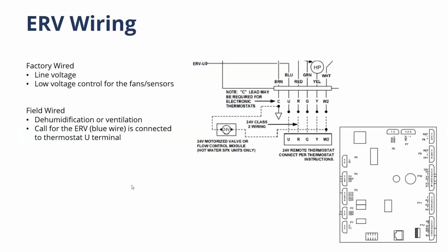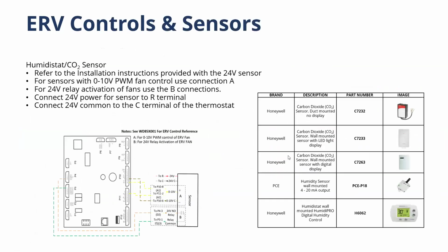So the ERV wiring, like I was saying, is very simple. All the systems that we've talked about today are single stage, with simple thermostat wiring. If you're doing the fresh pack ERV, then it's just an additional wire connecting the U terminal to the thermostat, which is that ASHRAE ventilation program that we talked about. There are additional ERV controls. If you have a focus on carbon dioxide or humidity issues in the building, we can certainly provide controls to focus in on those issues. And they can either be mounted centrally in the space, or in each room individually.